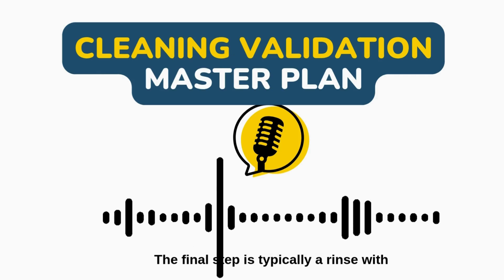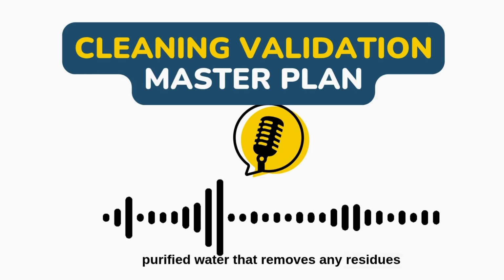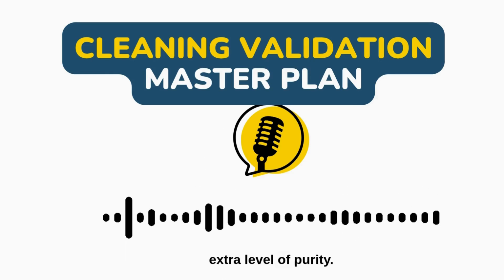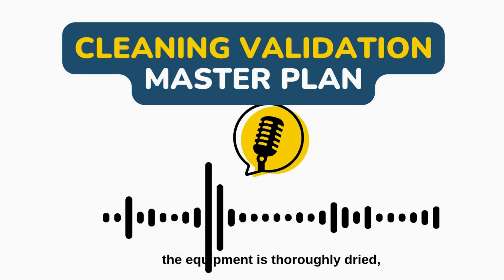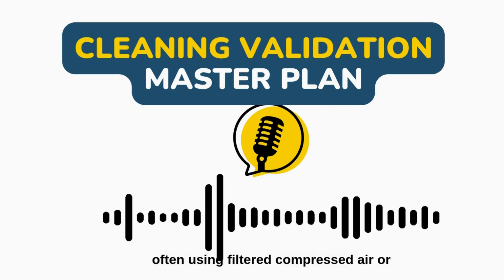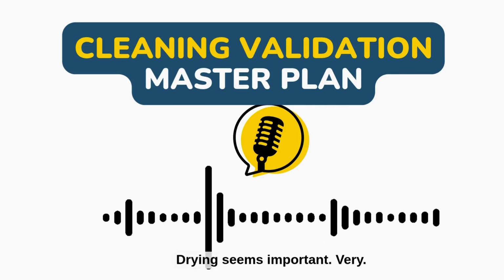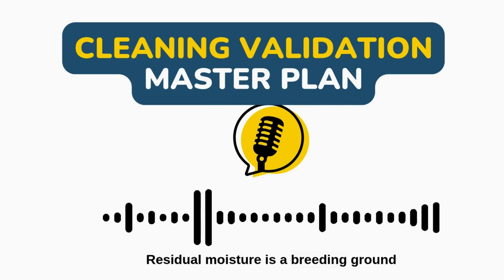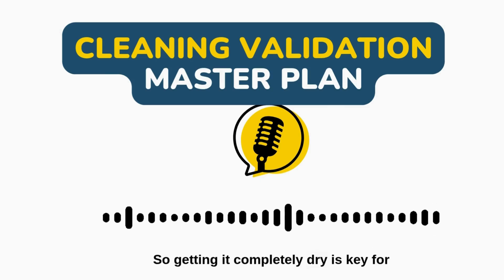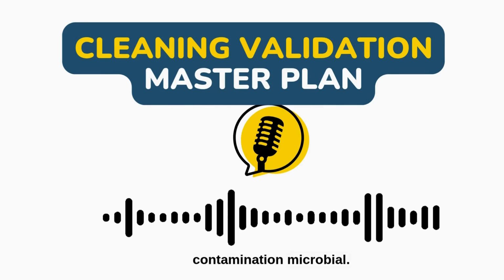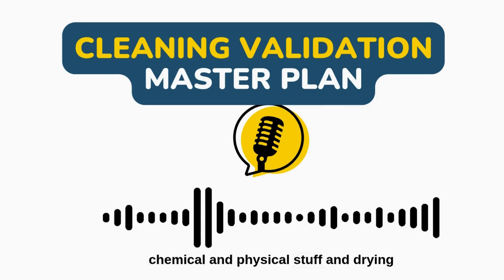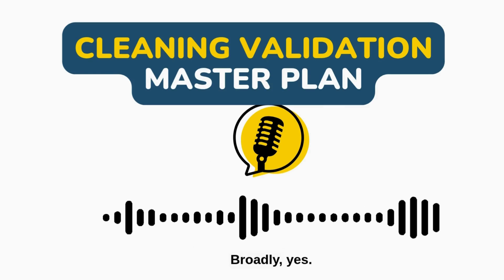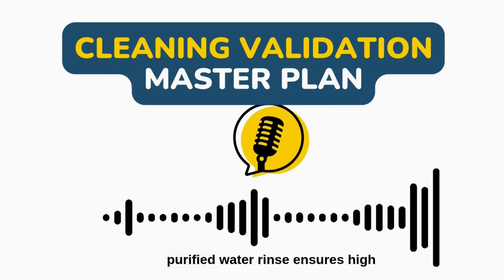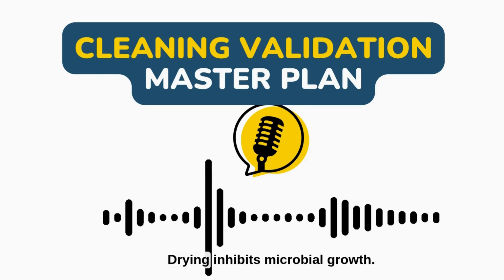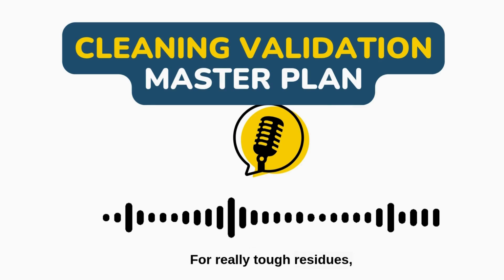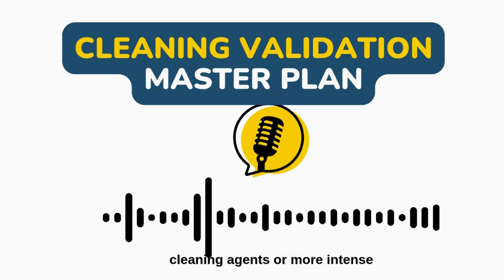The final step is typically a rinse with purified water that removes any residues from the potable water itself, an extra level of purity. And then, crucially, the equipment is thoroughly dried, often using filtered compressed air or a dedicated dryer. Drying seems important. Very. Residual moisture is a breeding ground for microbes, so getting it completely dry is key for controlling that third type of contamination, microbial. So the rinsing and scrubbing handles the chemical and physical stuff, and drying tackles the microbial risk. Broadly, yes. The water steps physically remove residues, and the purified water rinse ensures high chemical purity. Drying inhibits microbial growth. For really tough residues, they might use specific validated cleaning agents or more intense scrubbing.